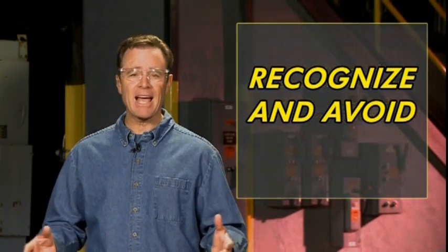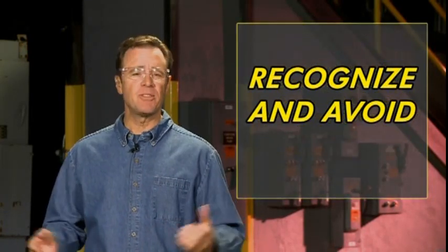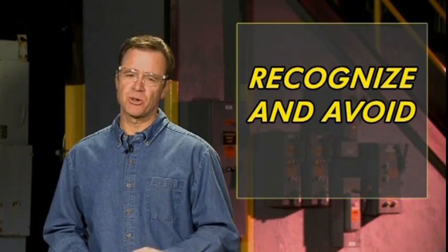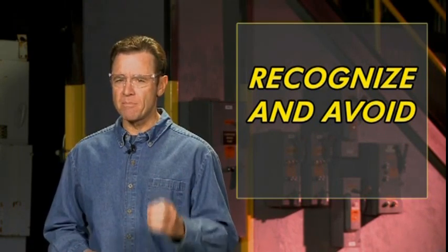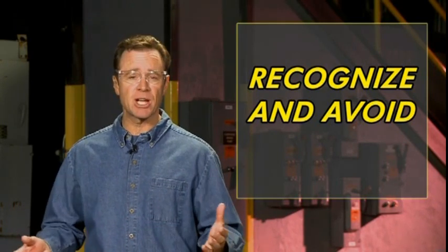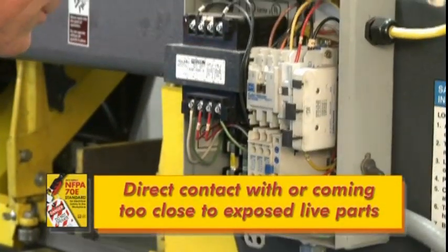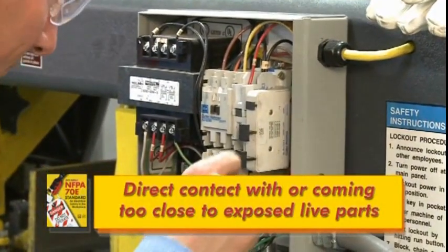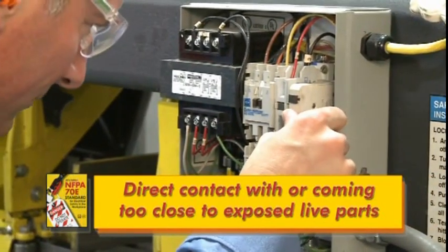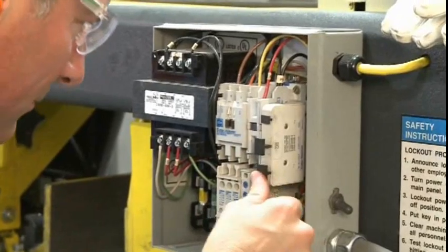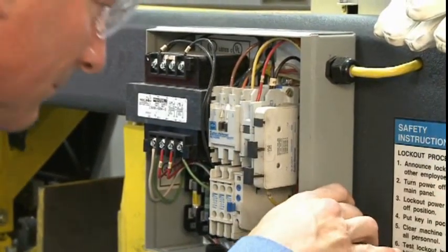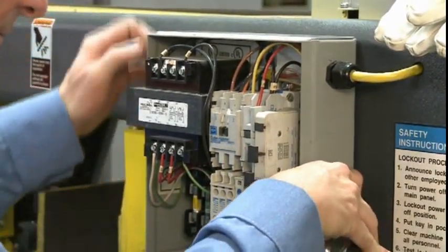Qualified workers must be able to recognize and avoid the hazards involved. And this requires that electrical workers understand that there are two main hazards presented by energized electrical equipment. The first hazard, direct contact with or coming too close to exposed live parts, as did this worker who neglected to wear rubber insulating gloves, can lead to an electric shock.